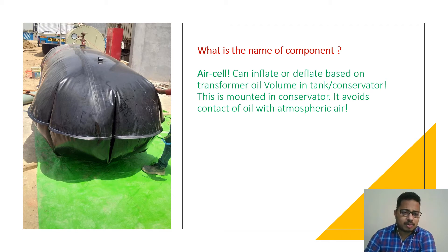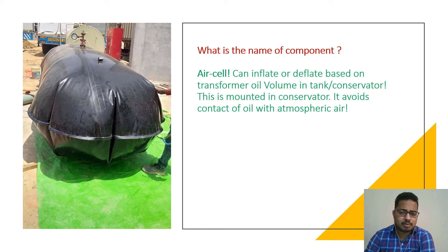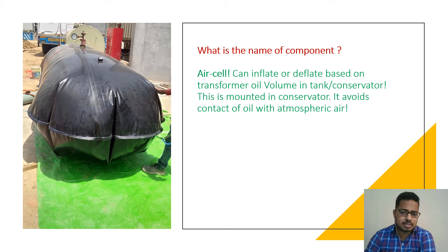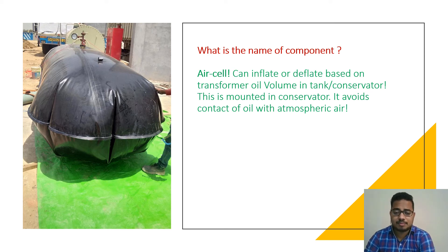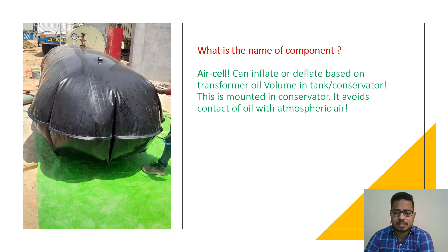Whenever oil is expanding, this air cell will deflate. Whenever the load is decreasing, oil volume decreases, so this air cell will come back to its normal state. If you have any questions or comments, please comment in the comment section. Thank you.